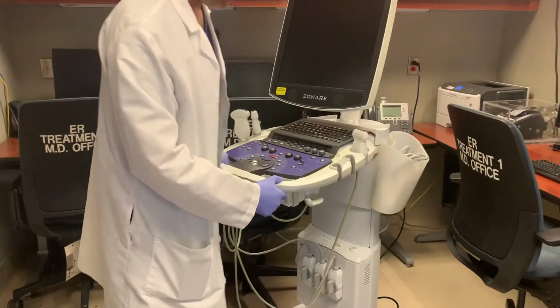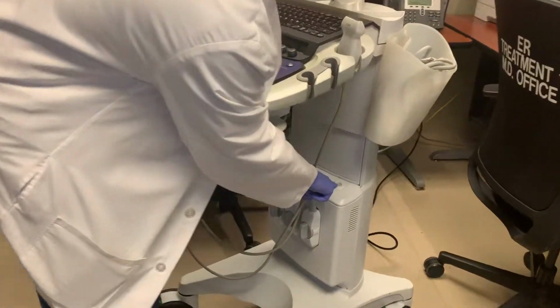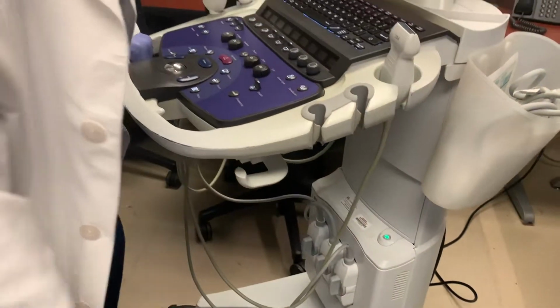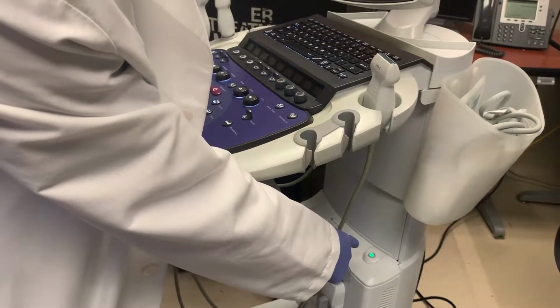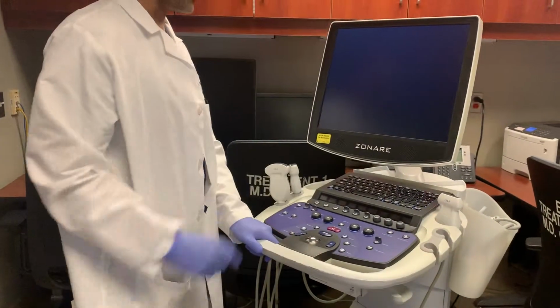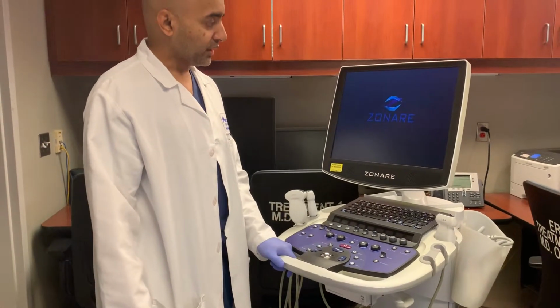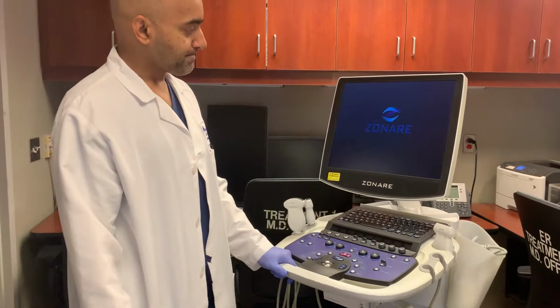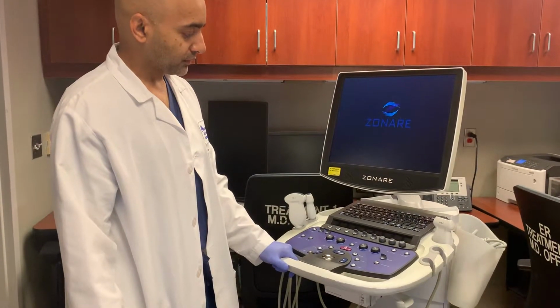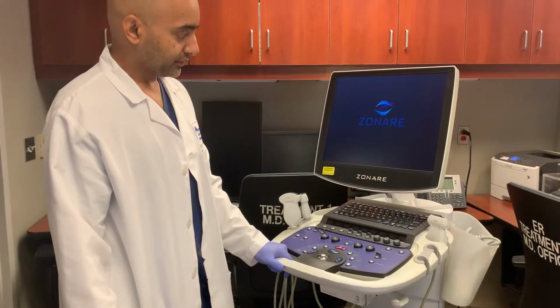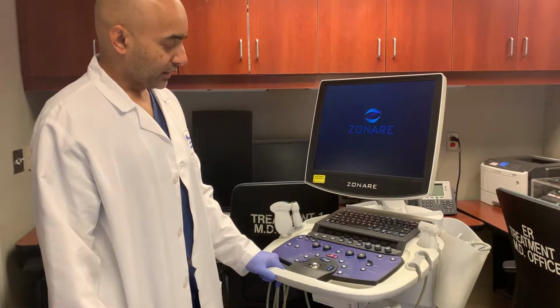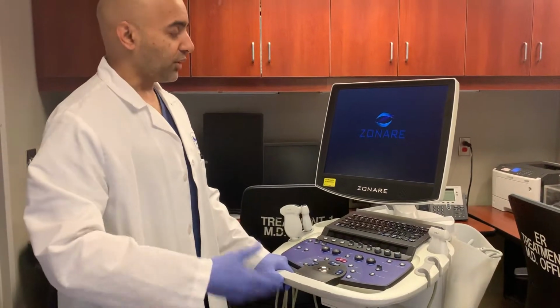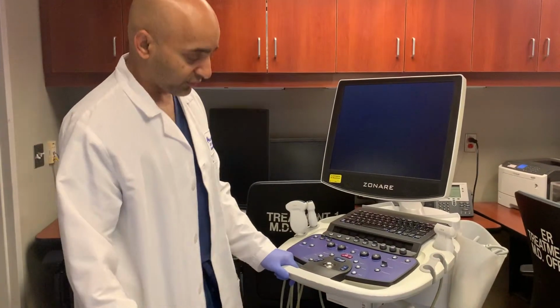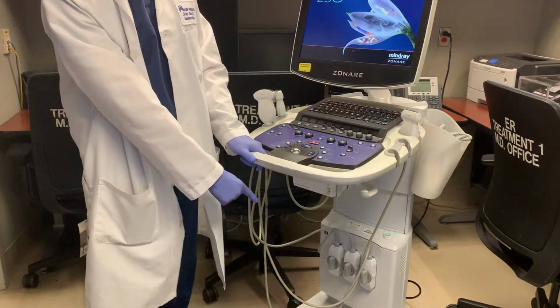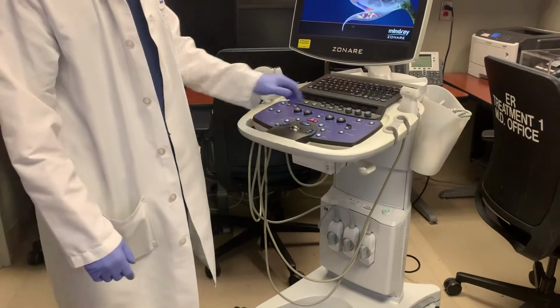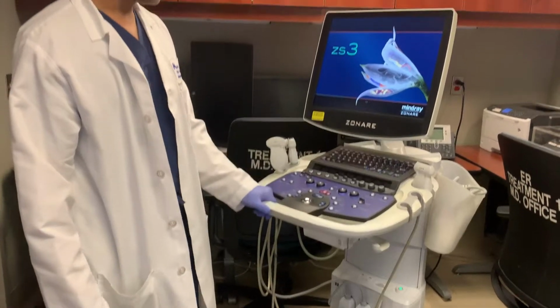First thing you're going to do after you plug it in is turn the on button, which is right here on the lower portion of the machine. Just press it and it'll turn green, and then you'll know that it's on. Once it's on, you'll see the image that says Zonare. It does take a few seconds to power up, so we'll just give it a second here. And when it powers up, it's going to default to whatever probe set you have as a default, but you can see that all three probes are connected, so you don't have to take them out and switch them. You can switch them with the keyboard or with the controls on the keyboard.